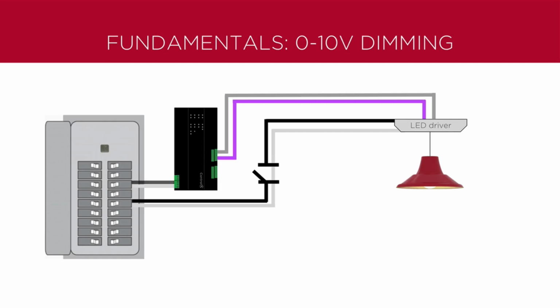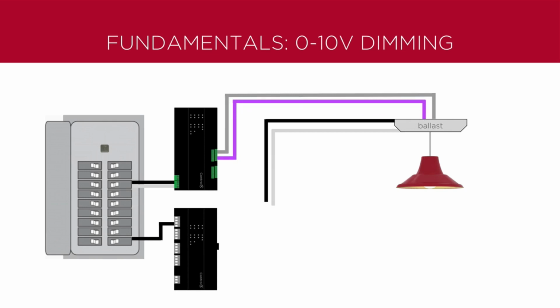A high voltage line in powers the module, and high voltage into the fixture powers the LED driver and the actual load. Low voltage commands from the module to the driver control the brightness of the load. And with LED drivers, full off commands are generally included. If the driver or ballast does not have an off command, a relay module can switch the on-off power to the ballast or the driver.